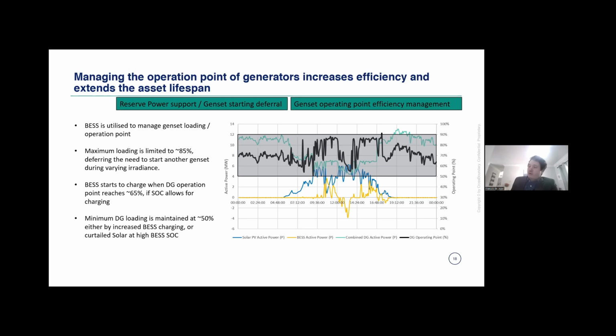And if our renewable penetration or the load drops, not allowing us to inject as much solar PV, only then do we start to curtail the solar PV plant in order to maintain the minimum loading on our generators at 50%.